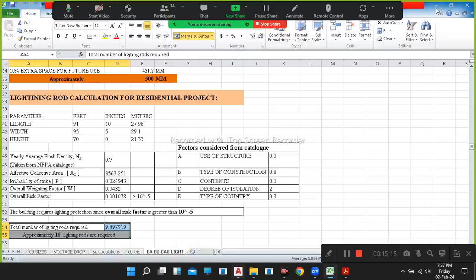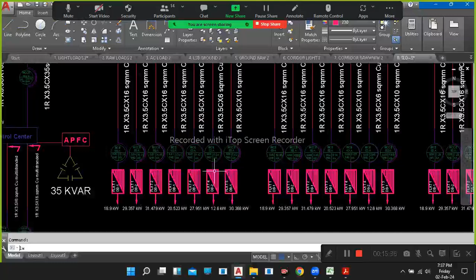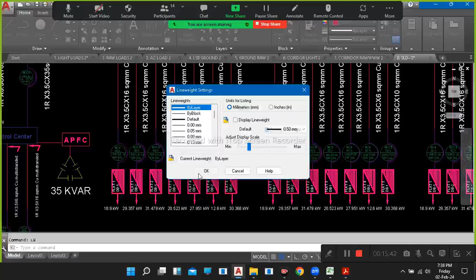But if I want to do this transformer, generator, UPS, and cable size, first of all we should know the load of each and every flat. Yes or no? Yes, sir. So when you get this total load, for example, when you get the DB load, once you get the DB load, then adding up the DB loads, you'll get the SMDB load. Adding up the SMDB loads, we'll get the MDB load. Then once you get the MDB load, for all the feeders, whatever the feeder number is given, for all the feeders, we need to do the cable size, circuit breaker, everything you will be doing in a sequence, right?